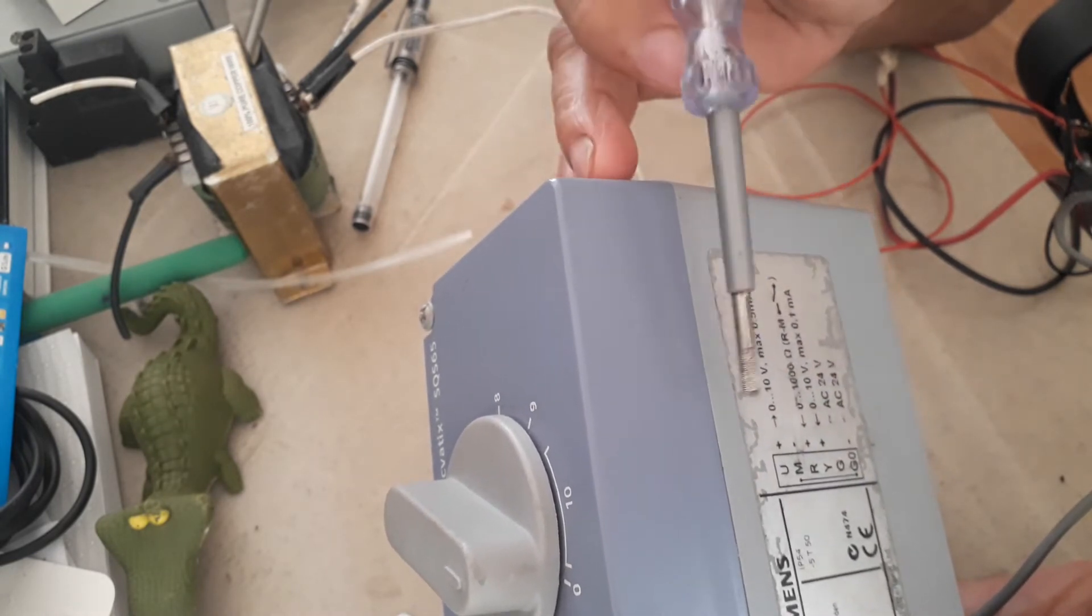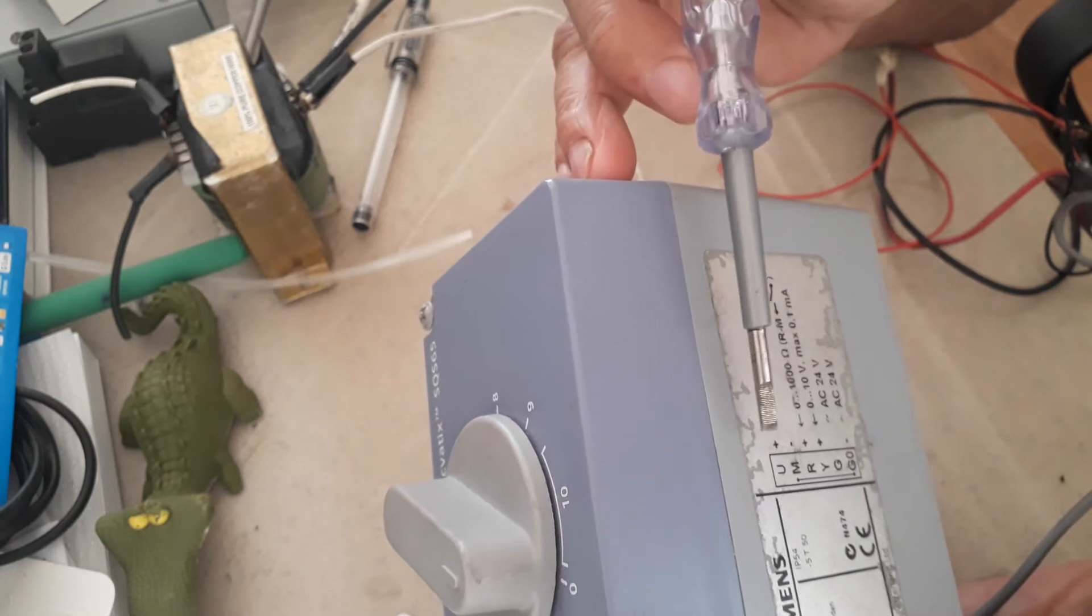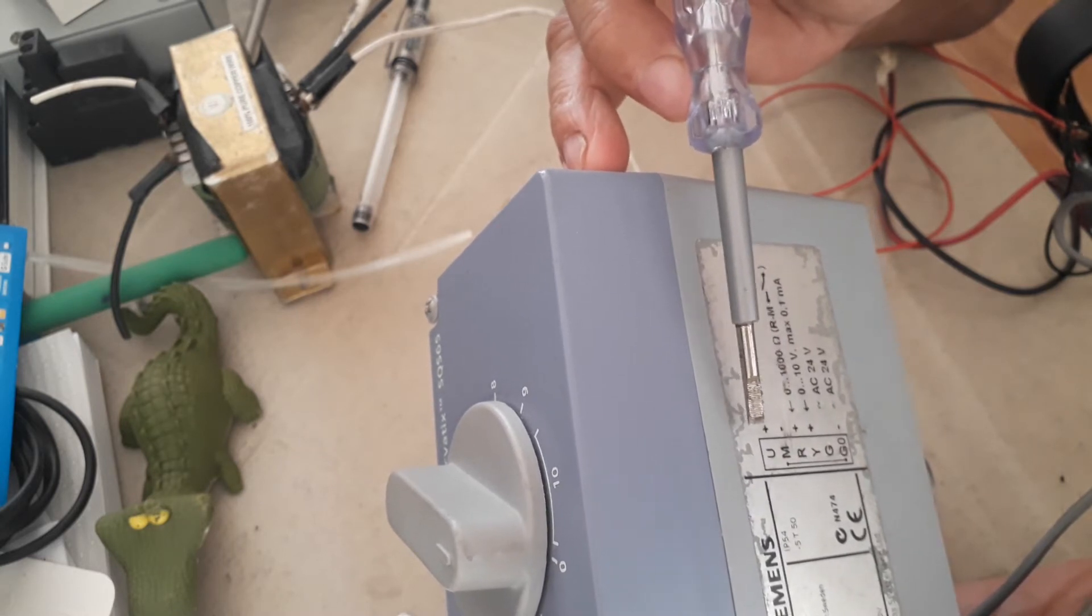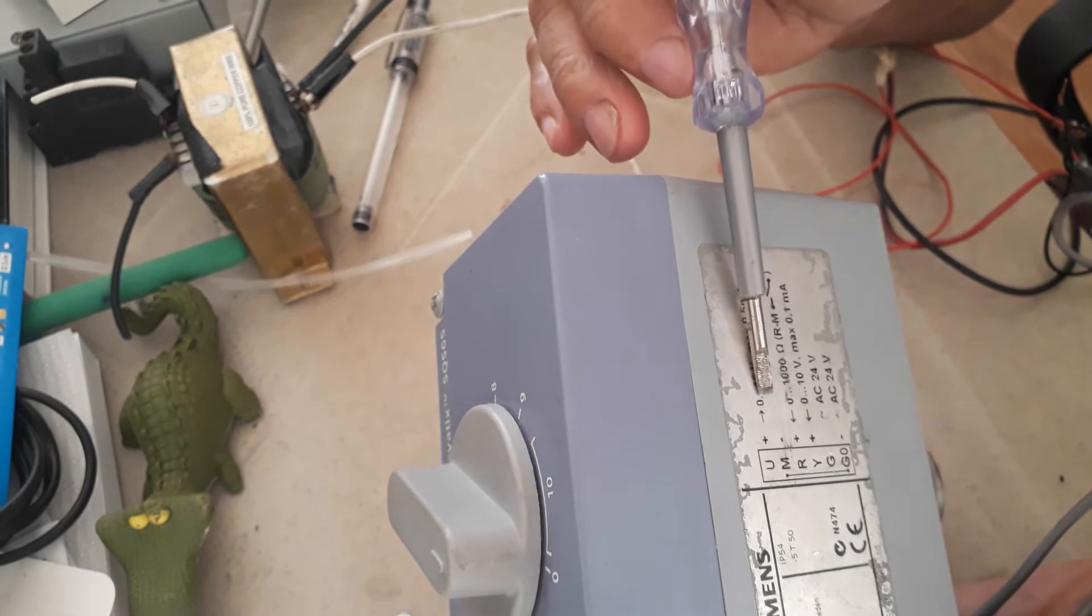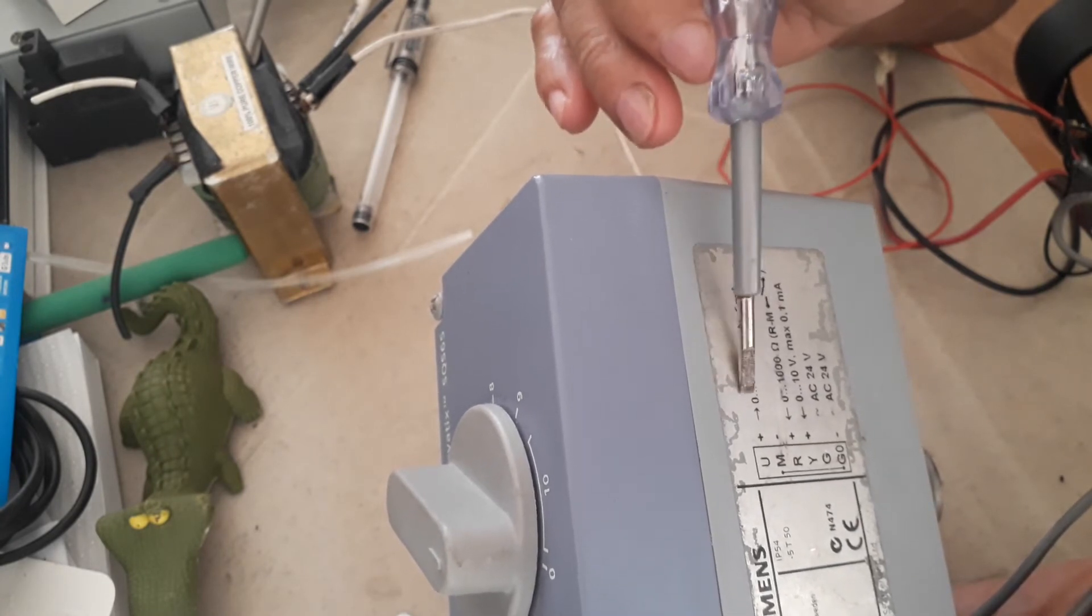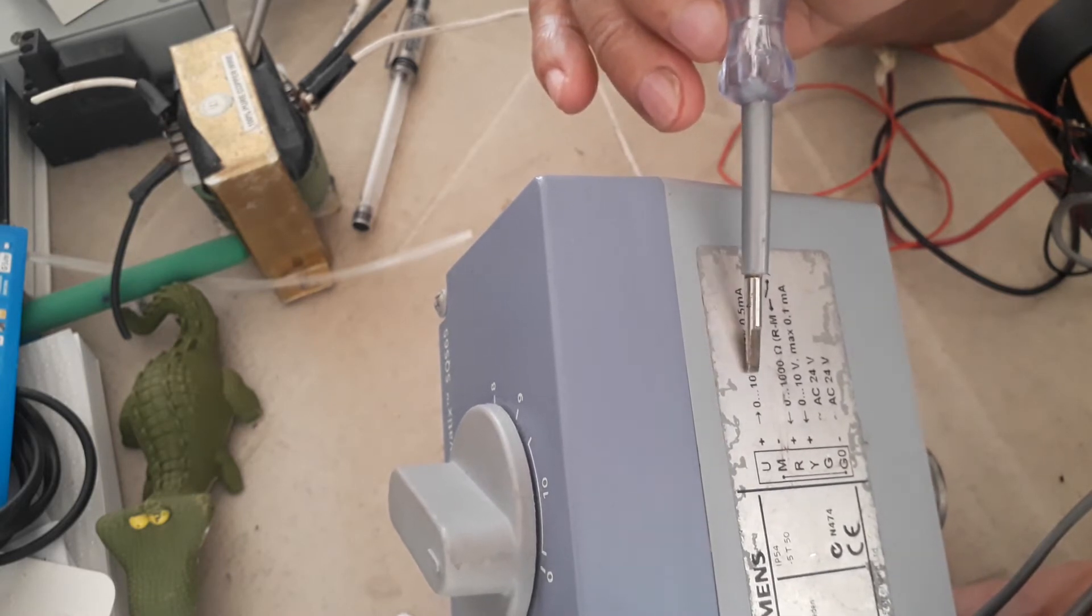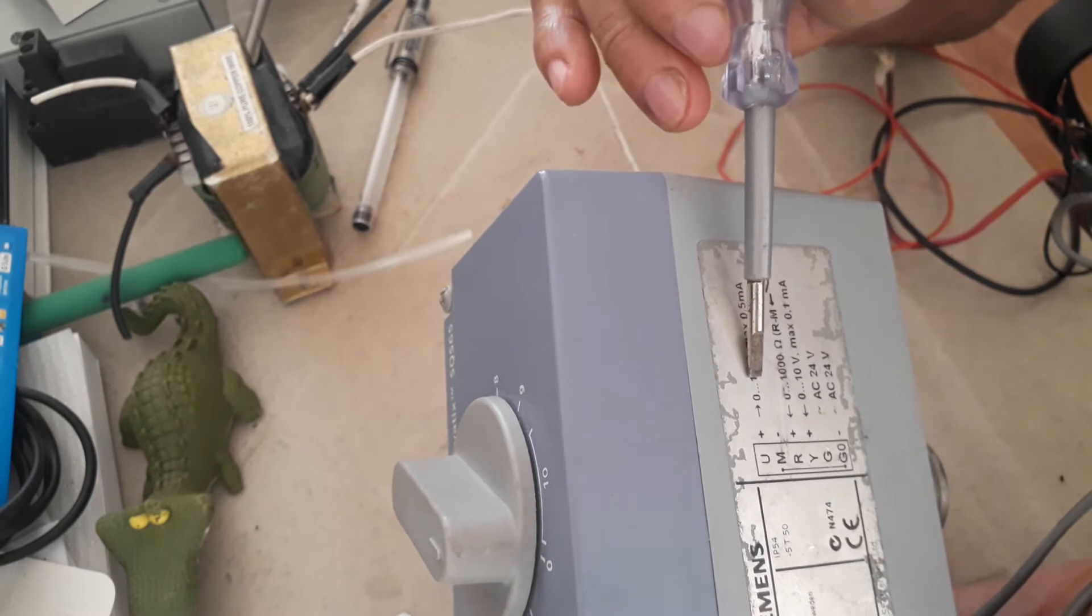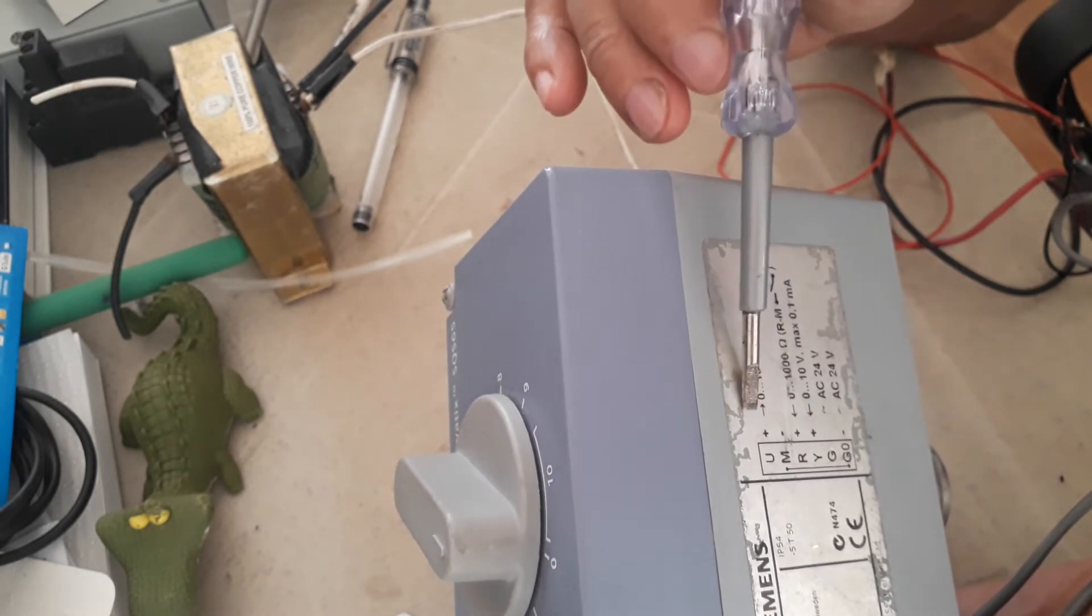U and M, you can use this for valve actuator feedback opening status. It will give also 0 to 10 volts to your DDC IO module. Your DDC will receive this feedback signal 0 to 10 volts. Meaning, 0 is closed, then 10 volts is 100% open. This is the feedback status from the valve actuator.